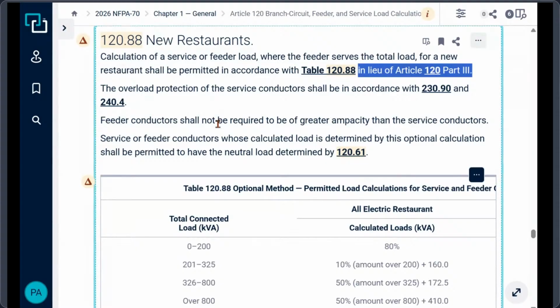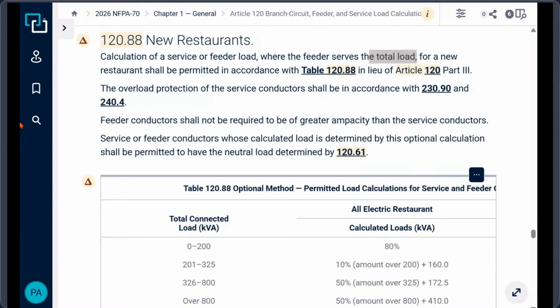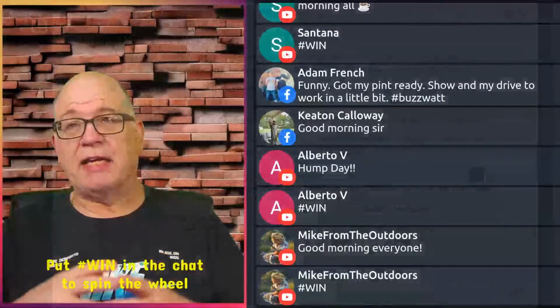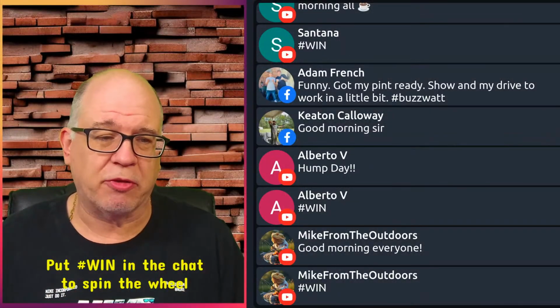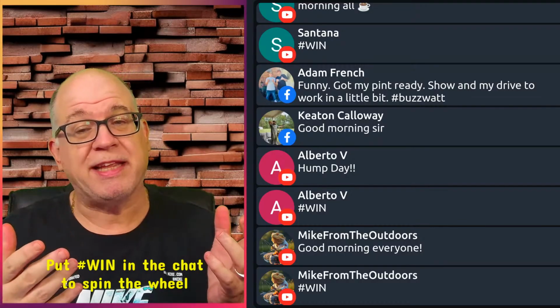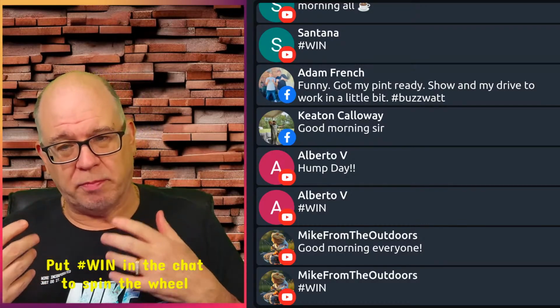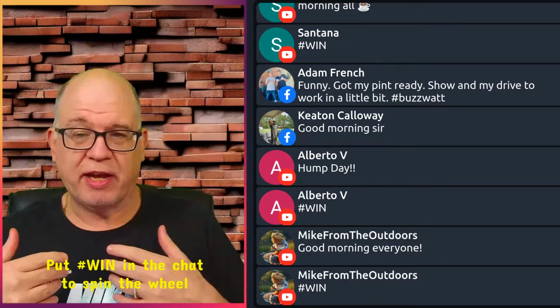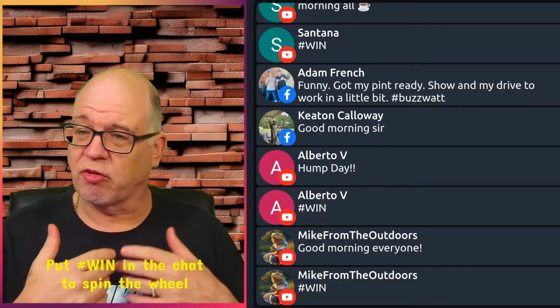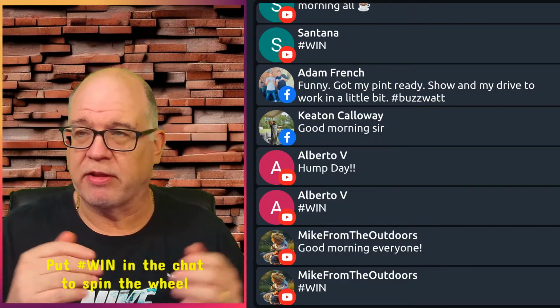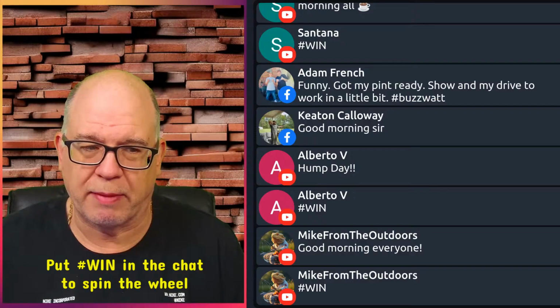Go with me? Okay, so what this means is that I can use this optional method to do the service, but I can also use it to do the feeder, where the feeder serves the total load. In other words, I could have these service equipment outside, and now the only thing coming into the building or the restaurant is feeders, because the service conductors are all outside. And that's very common in a lot of these commercial restaurant applications.